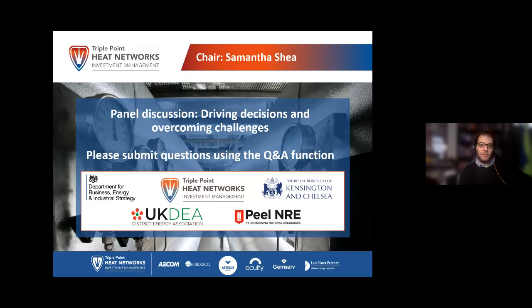For the heat network, the air source heat pump selected is a 1 megawatt unit. In terms of how big you can go, you can add multiple air source heat pumps. There are units up to 3-4 megawatts, but that depends on the type of refrigerant and the temperatures you're looking to supply. You can always go for a modular option where you add more units in series to supply more heat.